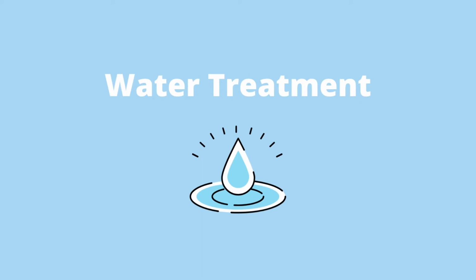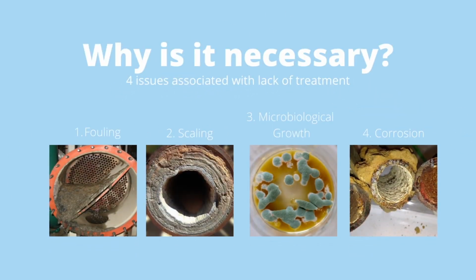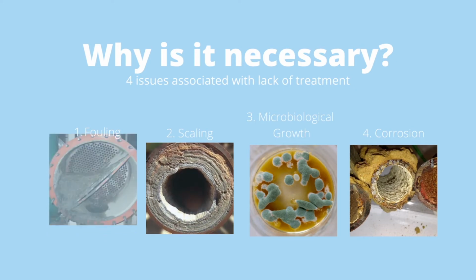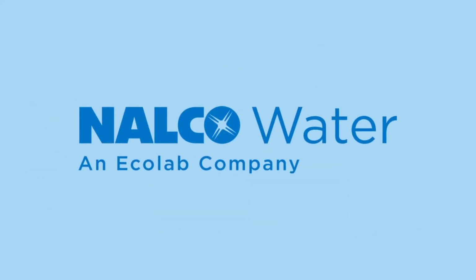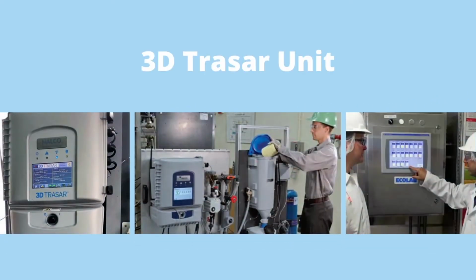In order to maximize the life expectancy of equipment, keep power consumption low, and prevent downtime for cleaning, water treatment is required and necessary. More specifically, water treatment is needed to prevent issues such as fouling, scaling, microbiological growth, and corrosion. These issues can lead to reduced productivity, increased repair costs, a delayed production schedule, and decreased plant efficiency. Nalco is the contractor hired by UNC to supply chemicals and create a water treatment program to fit the needs of chilled water. They monitor the system continuously with the use of 3D TRASAR units. The system sends alarms, notifications, and manages inventory. Without Nalco, the chilled water plants would likely have an extremely difficult time supplying the campus needs with chilled water.